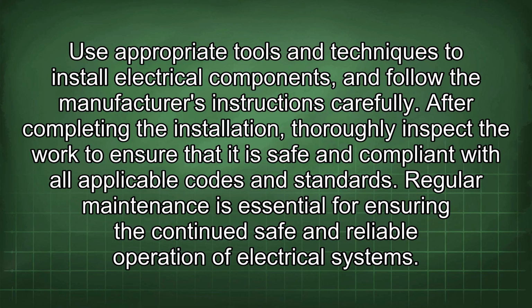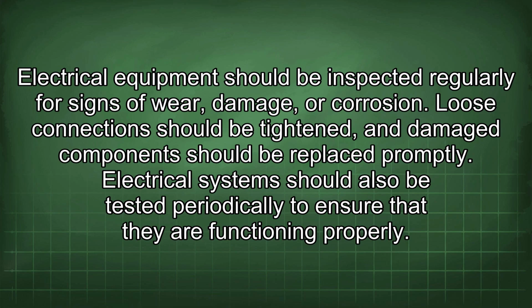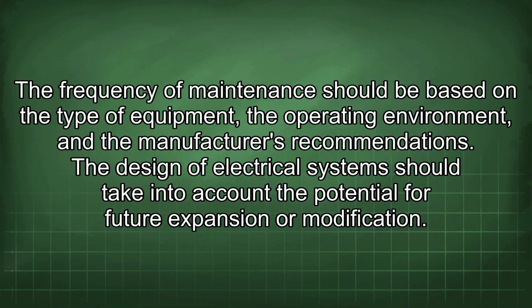Regular maintenance is essential for ensuring the continued safe and reliable operation of electrical systems. Electrical equipment should be inspected regularly for signs of wear, damage, or corrosion. Loose connections should be tightened, and damaged components should be replaced promptly. Electrical systems should also be tested periodically to ensure that they are functioning properly. The frequency of maintenance should be based on the type of equipment, the operating environment, and the manufacturer's recommendation.